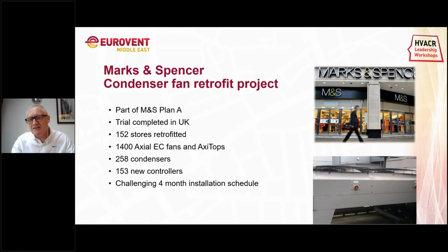The fans help maintain a constant pressure throughout the system, especially in the UK where we get very low temperatures in winter, unlike the Middle East. So the fans were able to run at a lower speed and just keep the head pressure constant.